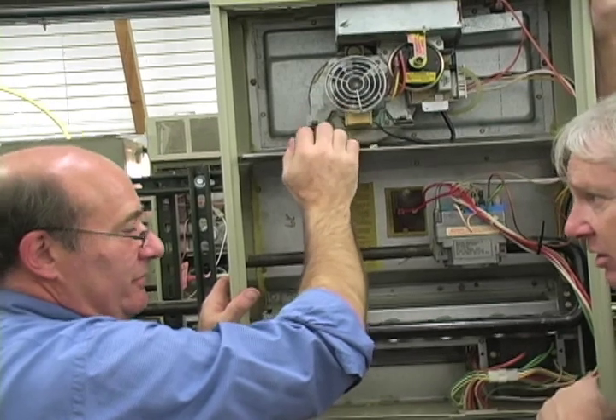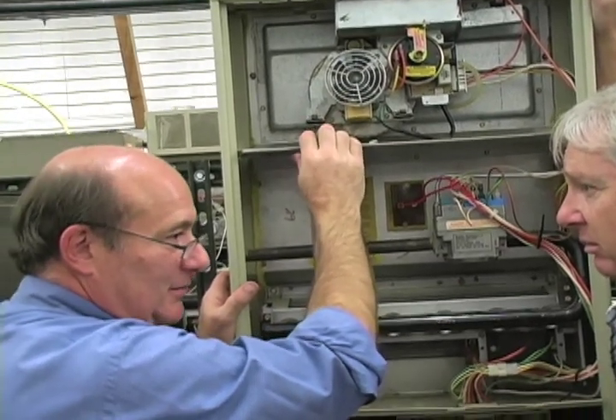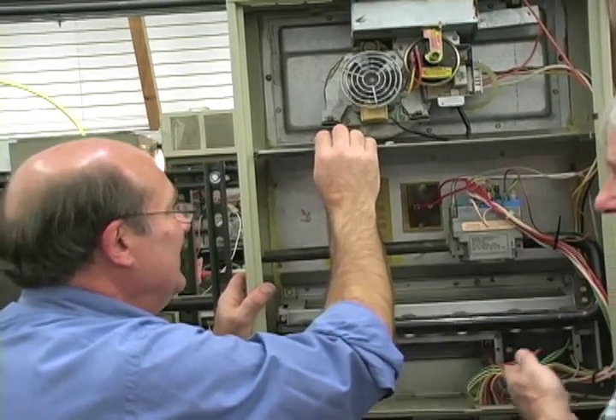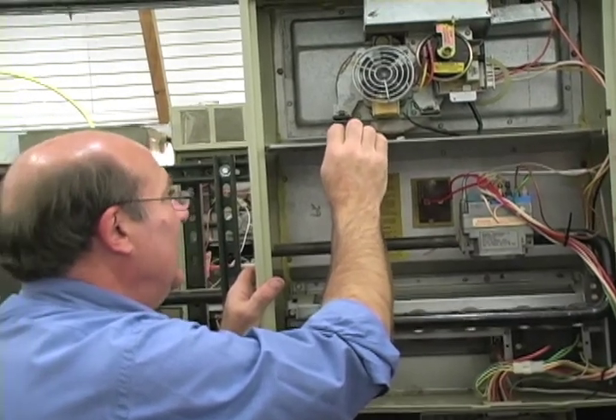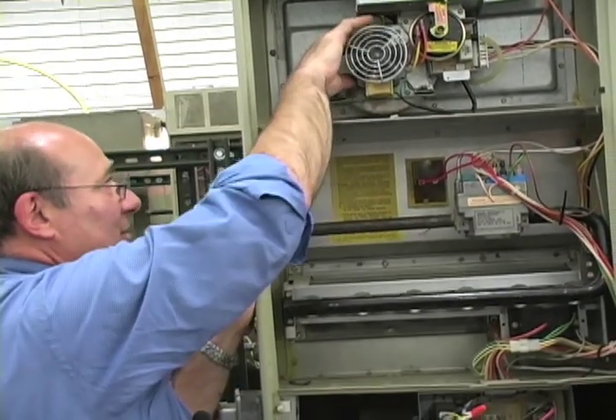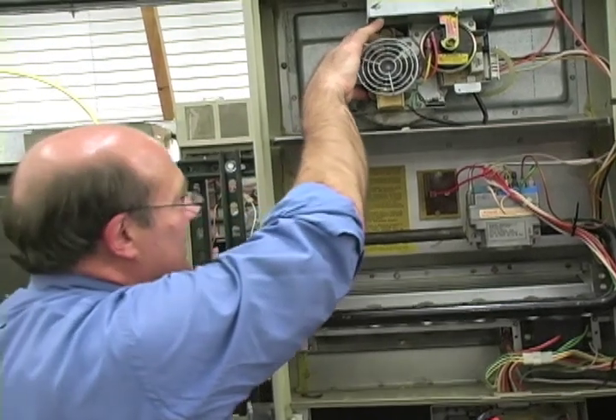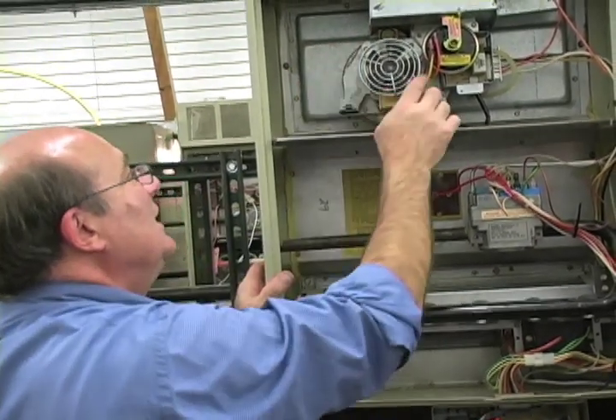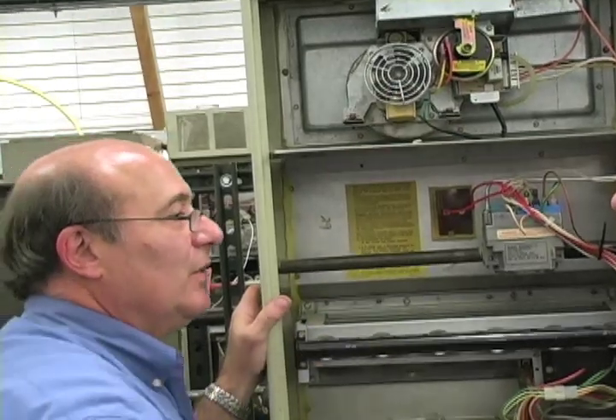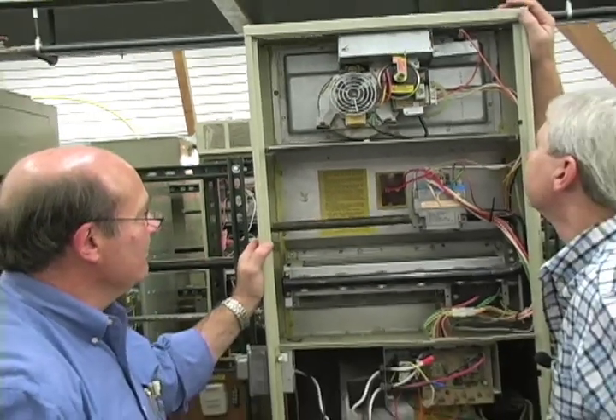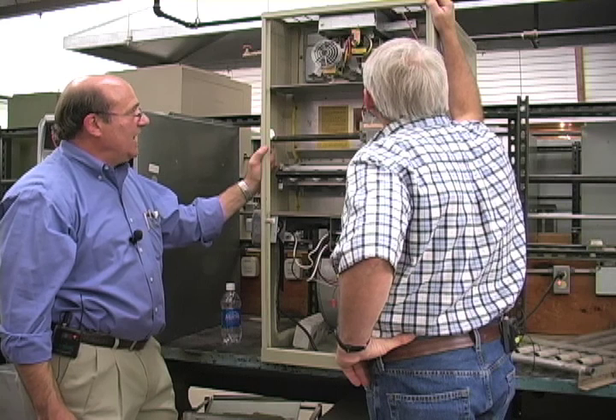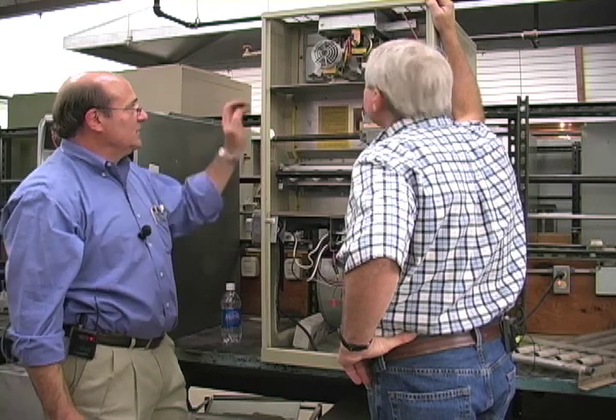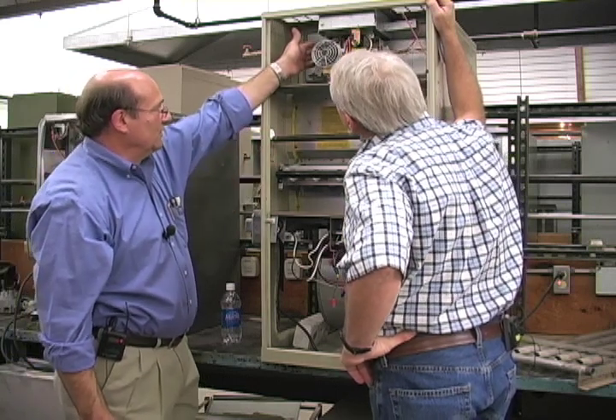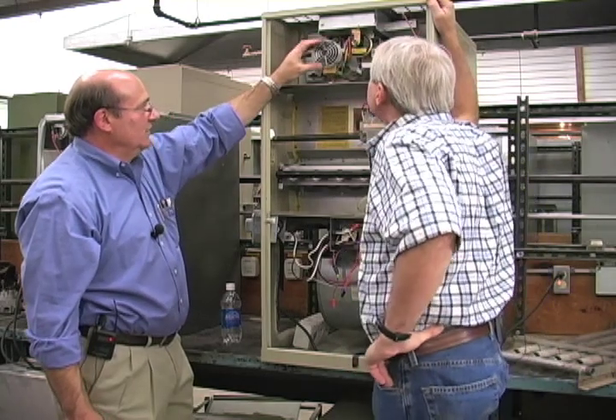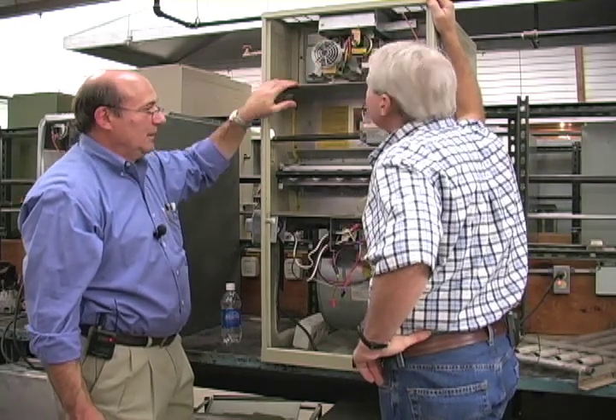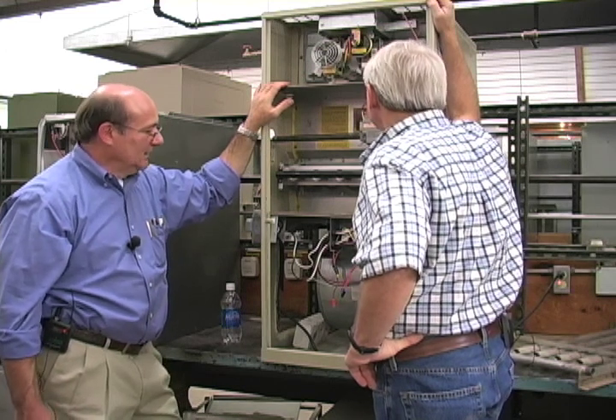In the heat exchanger? Well, the heat exchanger will never get to that temperature. At least, hopefully, it won't. Those are exhaust gas temperatures. The exhaust gas temperatures could get that high. So this combustion blower motor is bolted right up to this hot heat exchanger. This little fan here is just for cooling that fan motor, to kind of prolong the life of that system. So yeah, it's a single shaft, but a fan blade on each side. This side, of course, has a centrifugal fan or a squirrel cage little blower on it. And this one's just a really low pressure propeller type fan to cool that motor down.